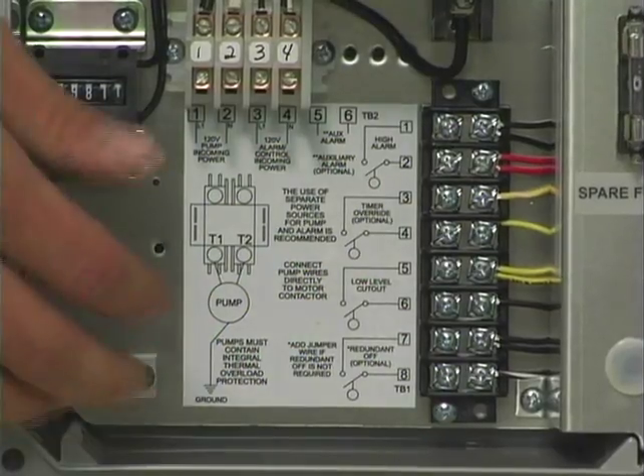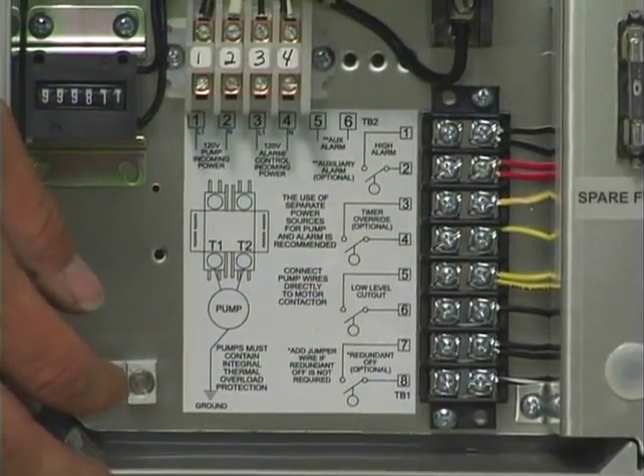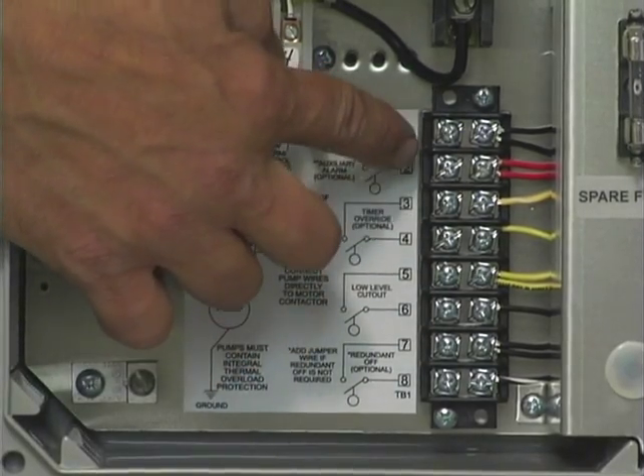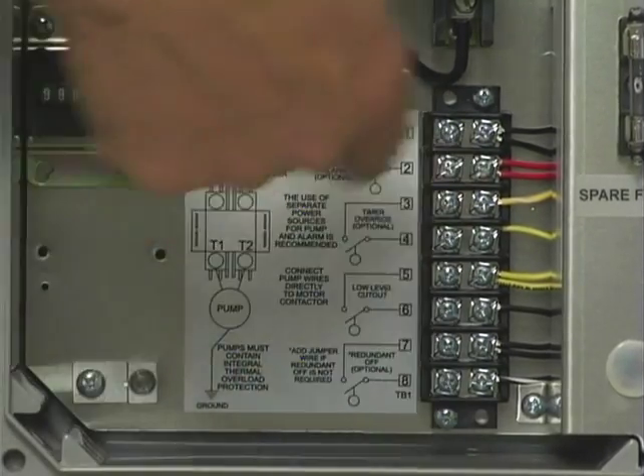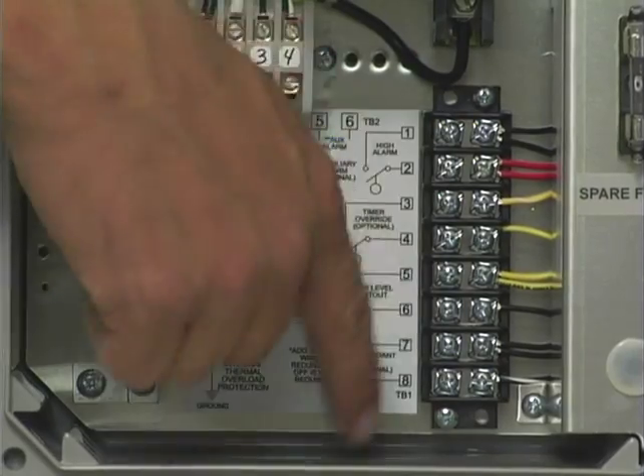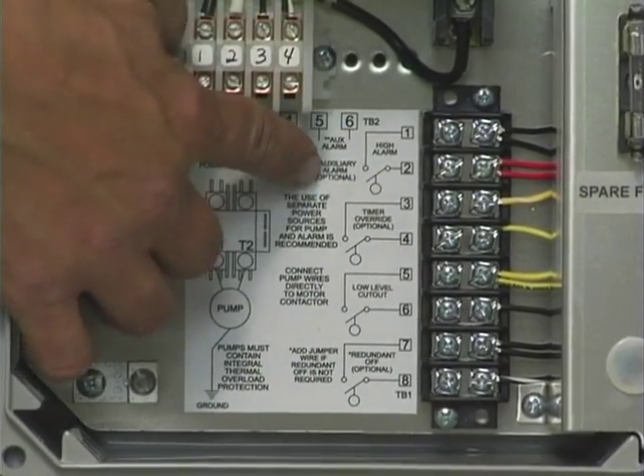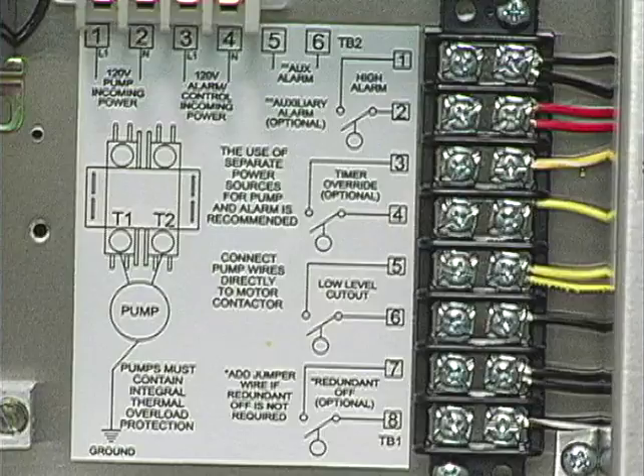The difference between the Rhombus control panel and the Orenco control panel is the terminal strip is different. On the Orenco control panel, the terminal strip goes this way. On the Rhombus, it'll go this way. But the good thing about it is it shows you what each float is doing, where each wire needs to land, basically.